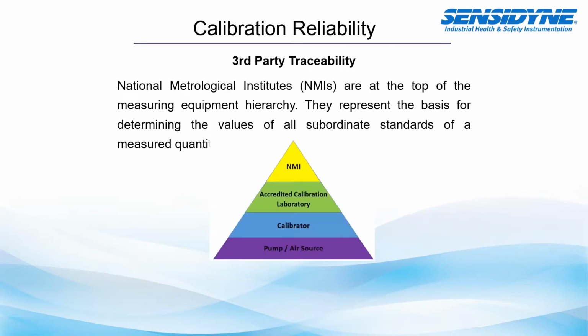The National Metrological Institutes are at the top of the measurement equipment hierarchy. They represent the basis for determining the values of all subordinate standards of a measurement quantity. So in this particular case, you see the NMI, then below it you'll have an accredited calibration laboratory, you'll have your calibrator, which will come with that traceable certificate, and then you'll use that calibrator to actually calibrate your field measurement or your field device for airflow, whether it's a pump or another type of air source.